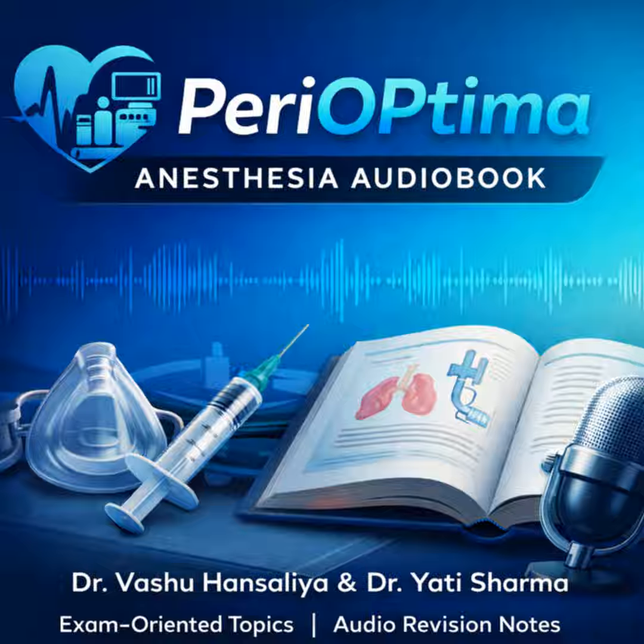Let's start with the absolute basics. When that question begins, describe anesthetic breathing systems, what is the fundamental definition, the purpose we need to articulate to get those first few marks on the board? Okay, so a breathing system is the assembly of components that connects the patient's airway, so usually via a mask, an LMA, or a tracheal tube, to the anesthetic machine or the ventilator. It's the conduit for gas exchange.